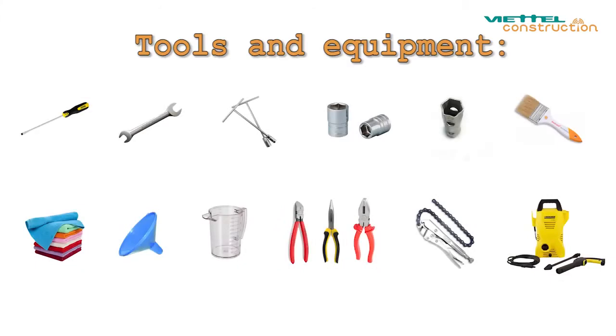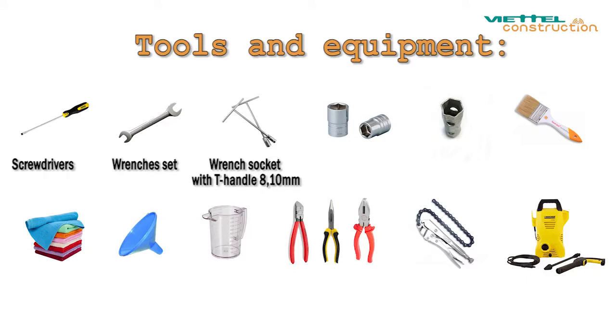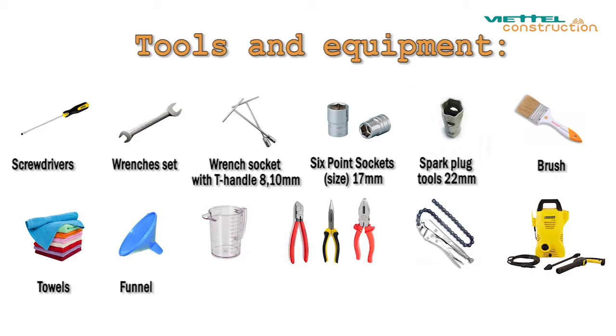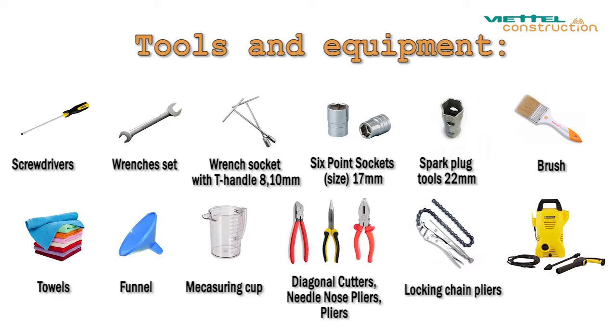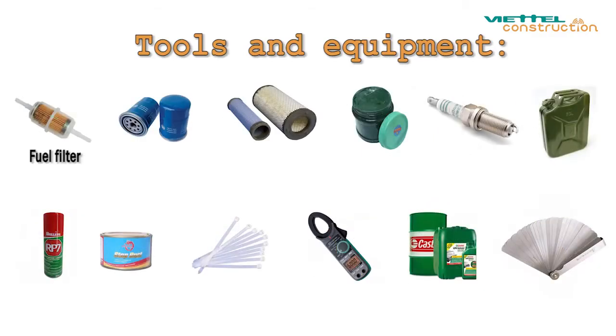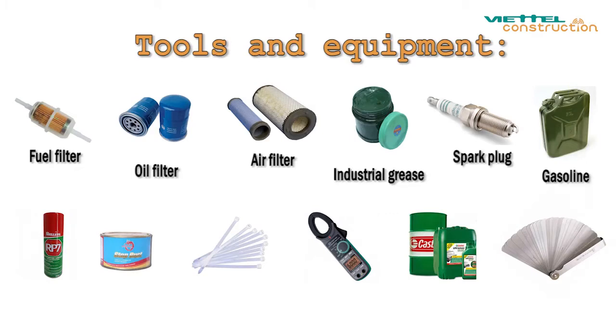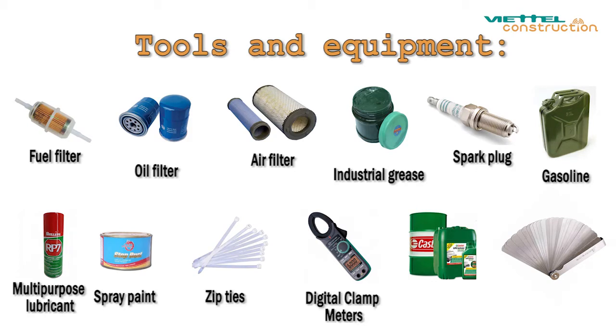To maintain the generator, we need to prepare the following tools and equipment: screwdrivers, wrenches set, wrench socket with T-handle 8, 10 mm, 6-point socket size 17 mm, spark plug tools 22 mm, brush, towel, funnel, measuring cup, diagonal cutters, needle nose pliers, locking chain pliers, booster pump, fuel filter, oil filter, air filter, industrial grease, spark plug, gasoline, multi-purpose lubricant, spray paint, zip ties, digital clamp meters, lubricating oil, feeler gauges.